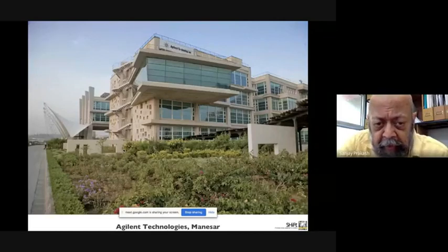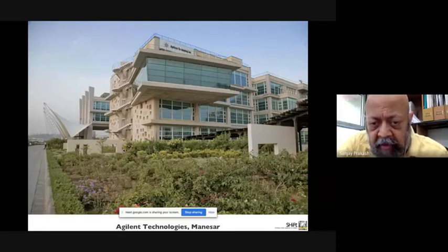And what it meant architecturally was that we had to work out the AHUs not only such that they were outside on the elevation, which you don't see in this picture, but also that they had something like 10 square meters of filter area, which meant that wherever the AHUs occur, a whole panel of windows is eliminated.